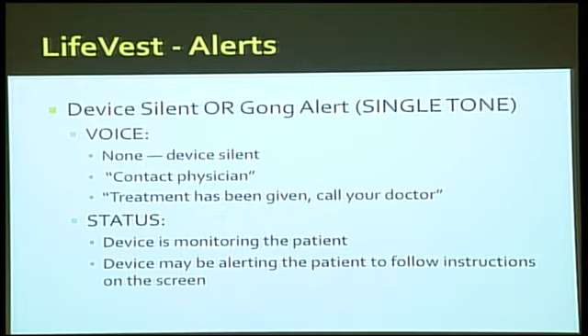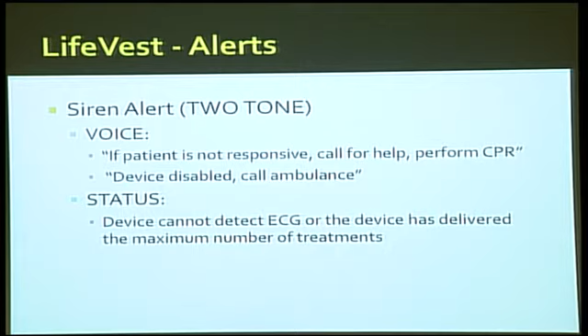If the patient's unconscious, you're watching the screen and it says, hey, I'm going to treat this patient. Treatment's been given means they've already been shocked. If there's a two-tone siren alert, and the patient's not responsive, the voice will say, call for help, perform CPR, or device disabled, call ambulance. That's what it'll tell the caregivers. That means the device can't detect the rhythm, or the device has delivered the maximum amount of treatments that it can. Some of these devices are set to deliver 6, some 9 consecutive shocks. Remember, these are very low dose shocks because they're external. It's probably less than 200.